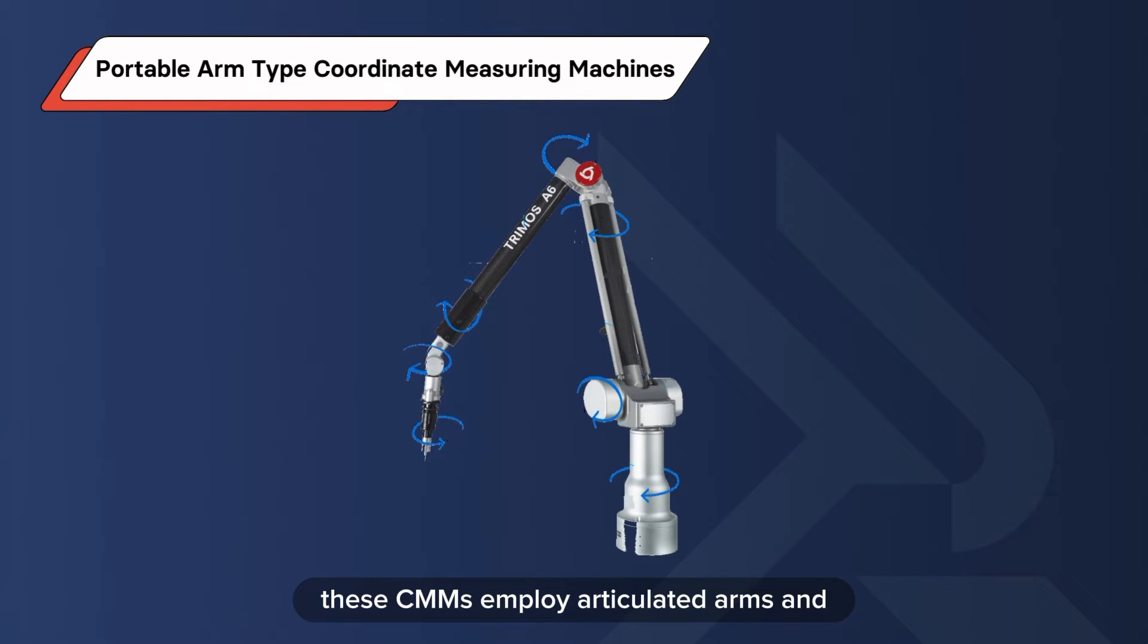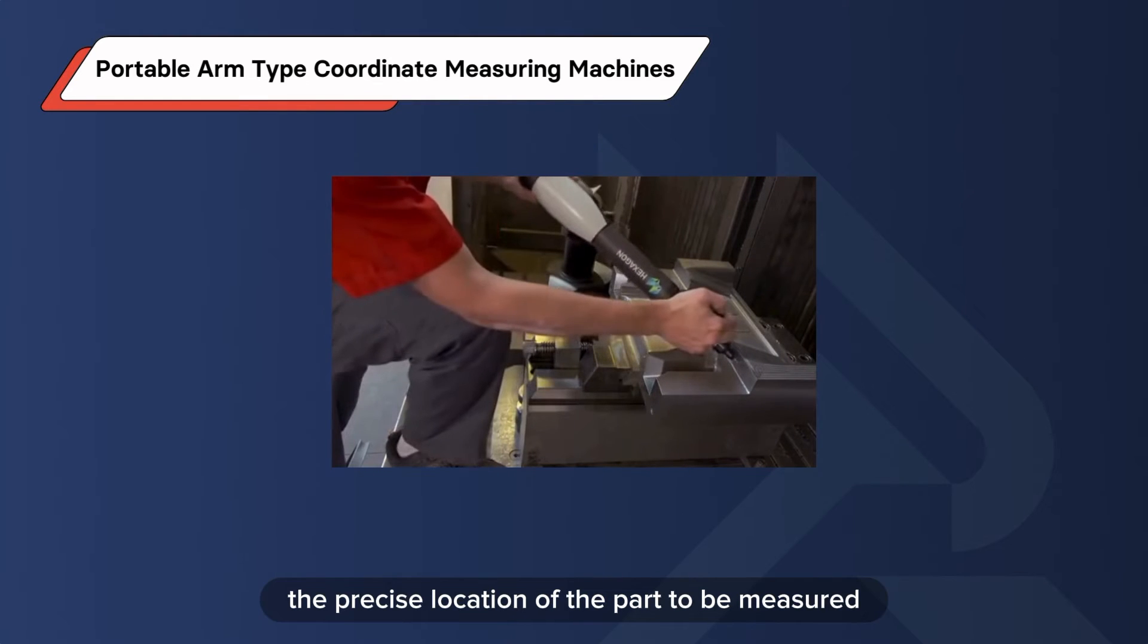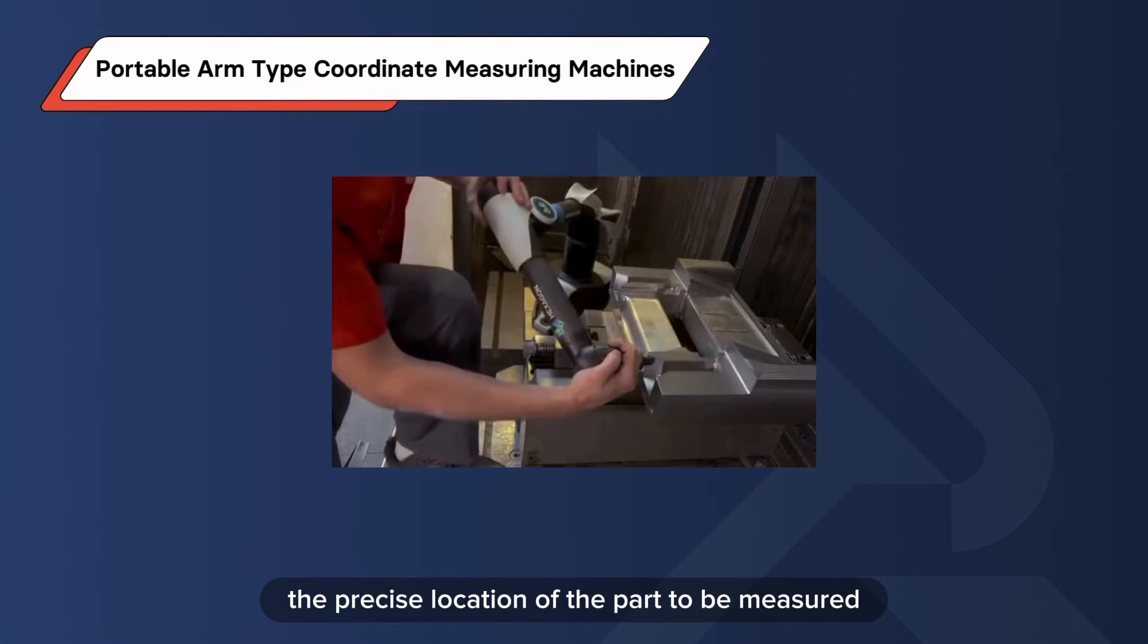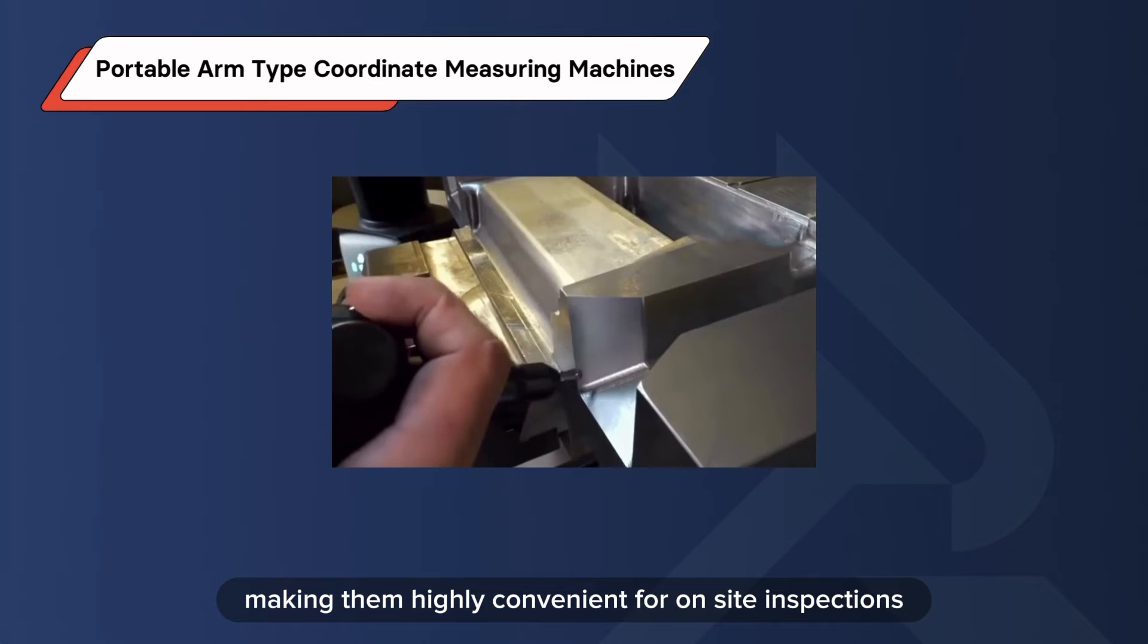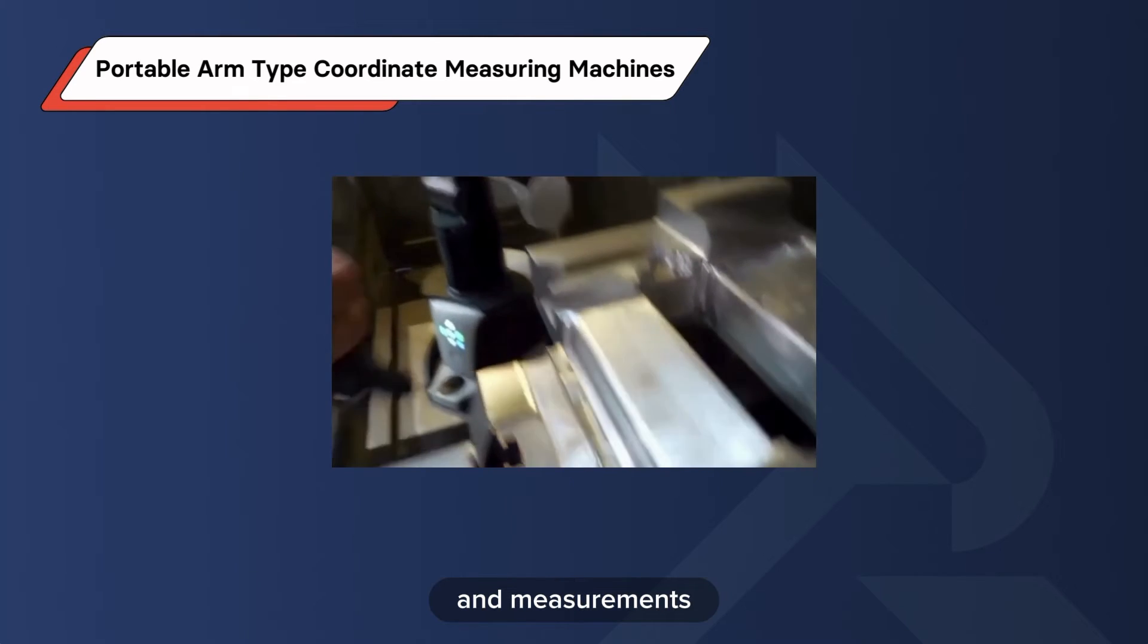Portable Arm Type Coordinate Measuring Machines. These CMMs employ articulated arms and calculate coordinates through rotary positioning, granting them greater versatility. They can be relocated to the precise location of the part to be measured, making them highly convenient for on-site inspections and measurements.